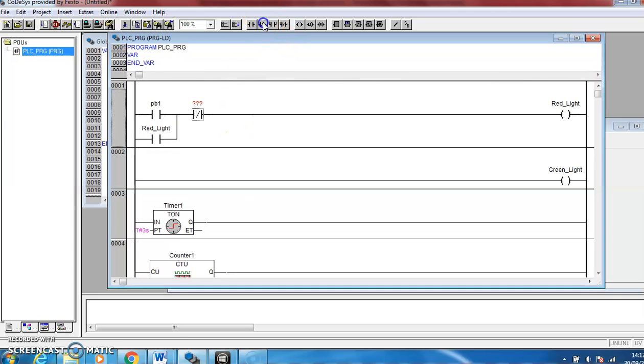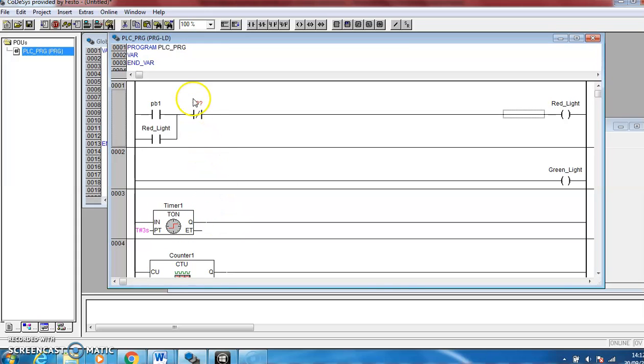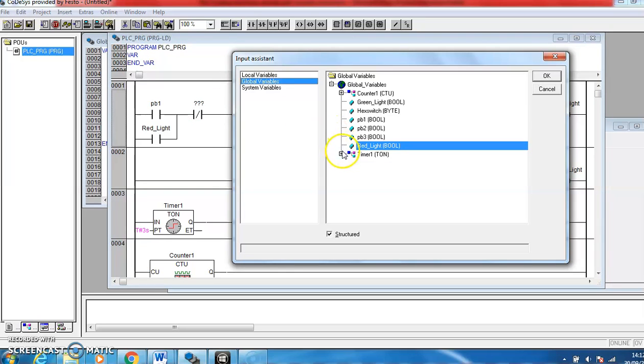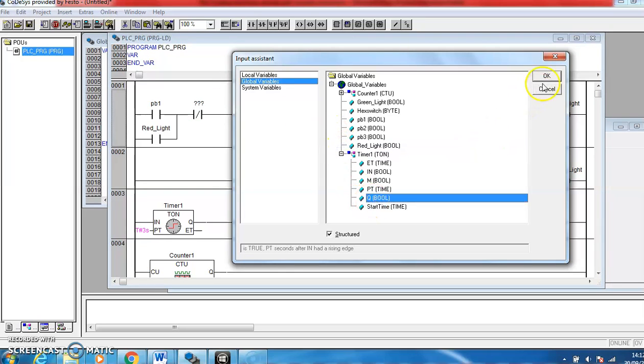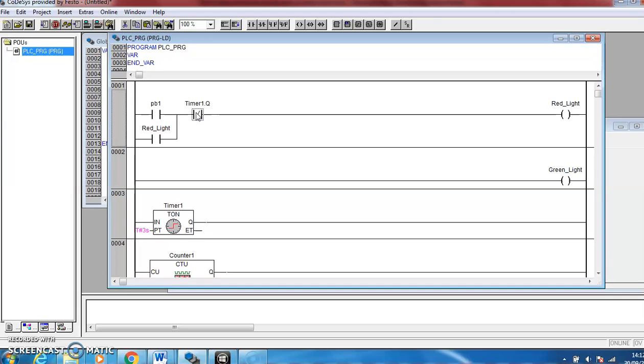And then we need a normally closed contact to put it off. So this normally closed contact, it says it must go off after a three second delay. So what we're going to do is use this signal from the timer. So the timer will get a signal in, it'll time for three seconds, then it'll turn on this Q value out. So if I use a normally closed contact from that Q value, the output value from the timer, then push button will come on, the red light will come on, the red light will stay on until the timer lapses, and when the timer lapses that contact will open and it will turn off the red light again.